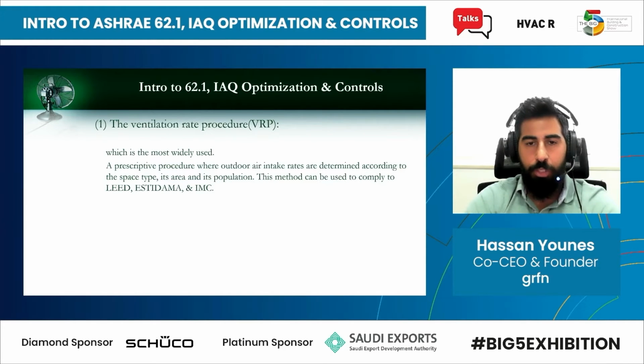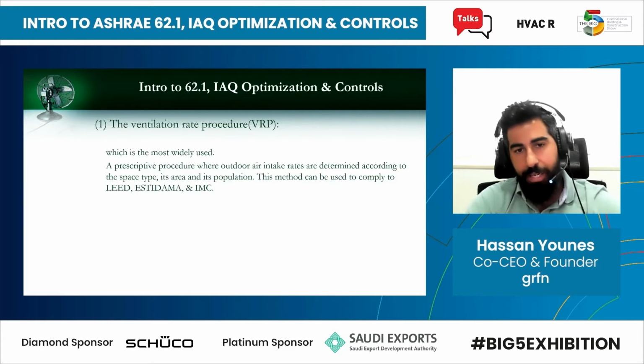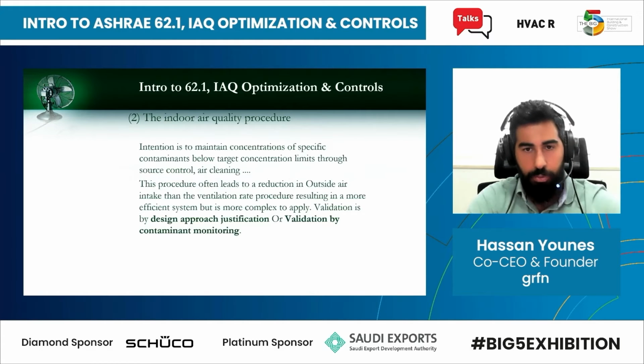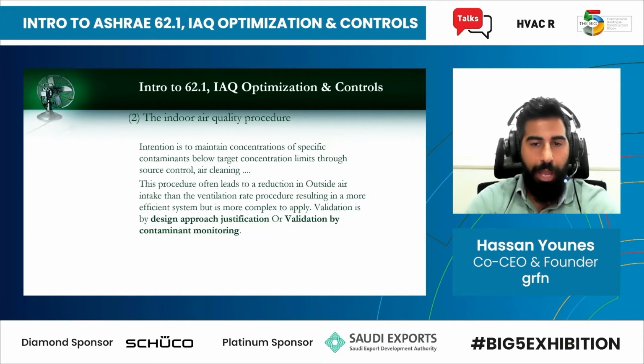So it's a prescriptive procedure where outdoor air intake rates are determined according to the space type, its area, and its population. So we'd go to that particular table in the standard, look at the type of occupancy, let's say an office building, and then we'll see that for an office building, it shows that 5 CFM, or 2.5 liters per second per person, is required, and around 0.3 liters per second per square meter is required for the area. So we check the area, check the number of people, and use that equation to come up with the required outdoor air that needs to reach that zone.